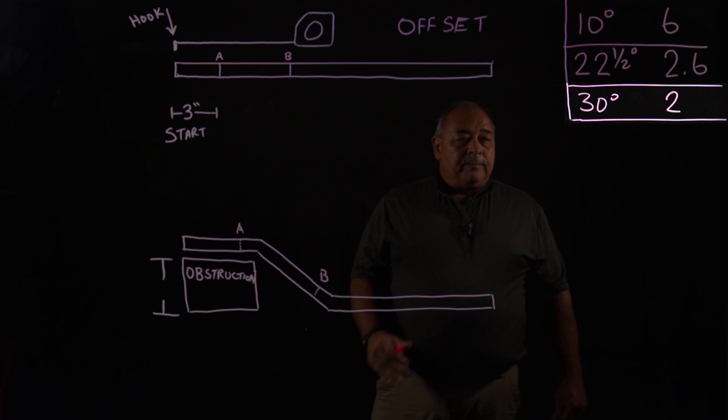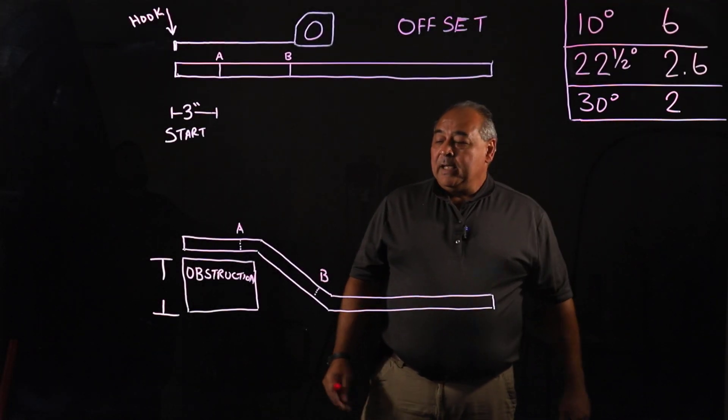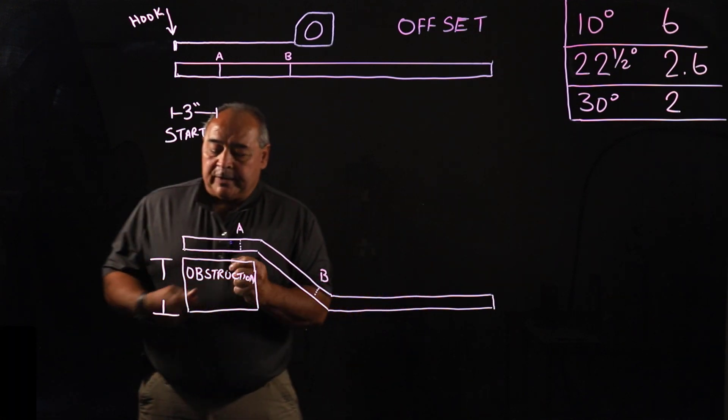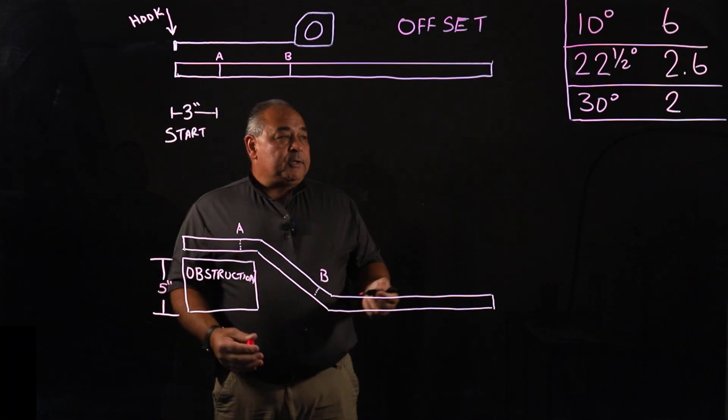But a 30 degree is so simple and it's so easy for us to remember. Your multiplier is 2. If this is five inches, and I'll go ahead and write the five inches over here, our multiplier is going to be 2.